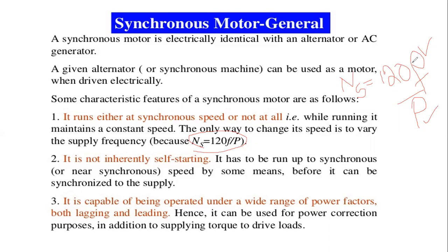When we change the frequency, the synchronous motor speed changes. Otherwise, it is a constant speed motor, running at the synchronous speed Ns. The only way to change its speed is to vary the supply frequency. Therefore, Ns is equal to 120 F by P.